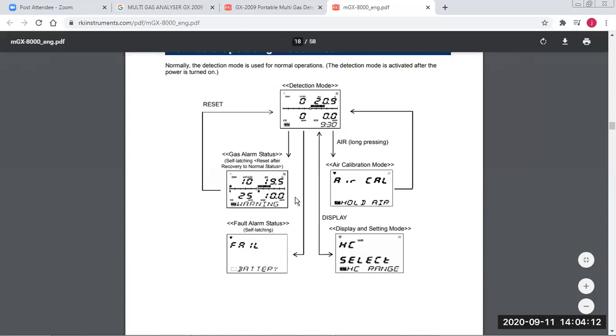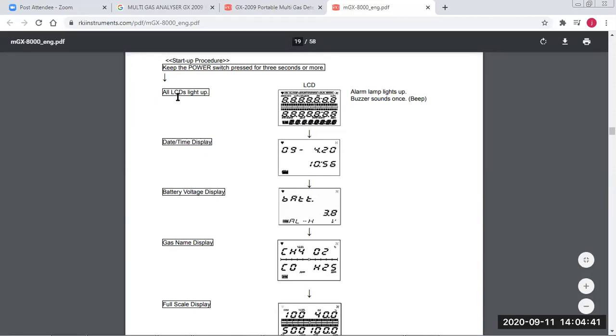Then we have the calibration mode, and how to enter it. After long pressing the air button, we enter the air calibration mode. And if you go to the menu, you can also enter the span gas calibration mode. So when you start the instrument, first all the lights will light up and it will show you the date and time. You can change it later if you want. Battery level and voltage. Then the gases: hydrocarbon or methane, O2, carbon monoxide and H2S.